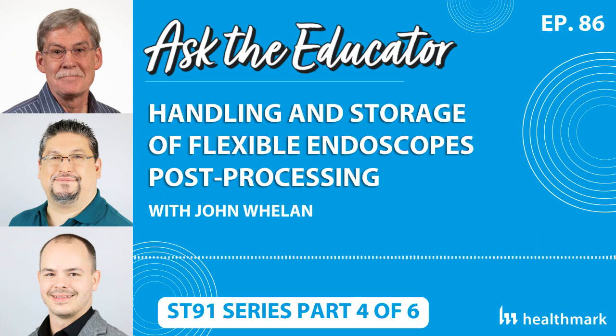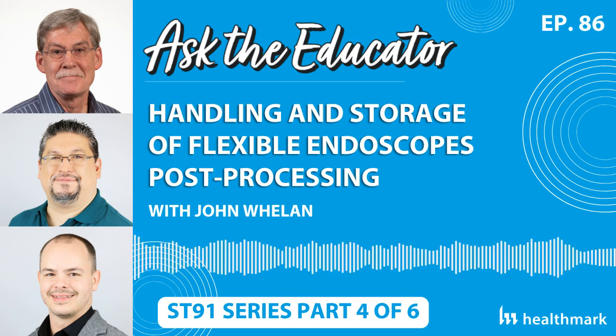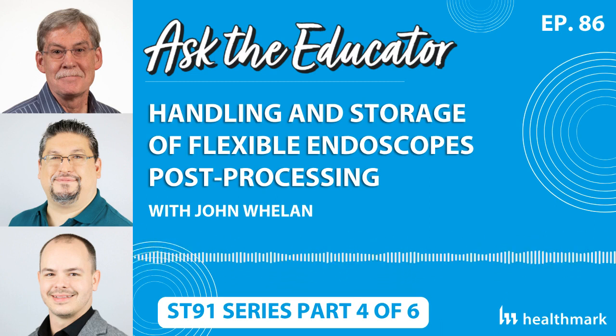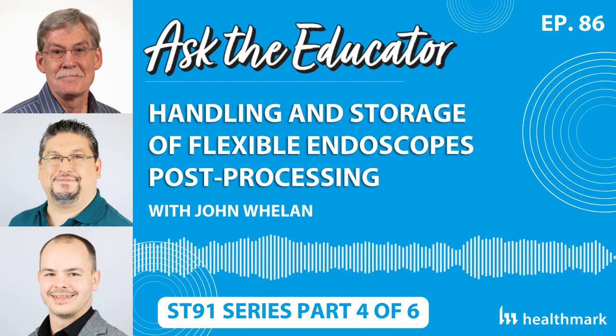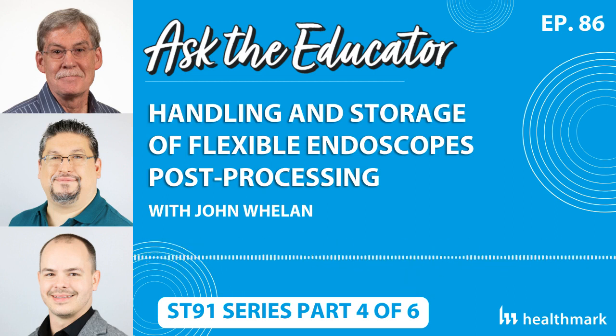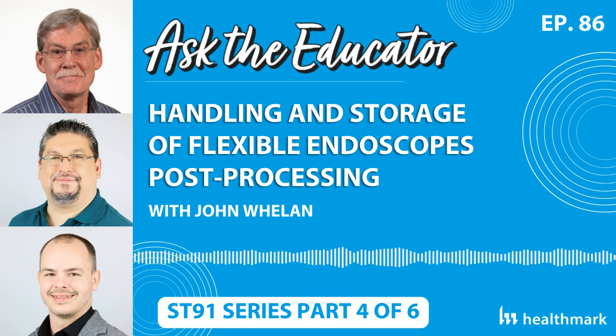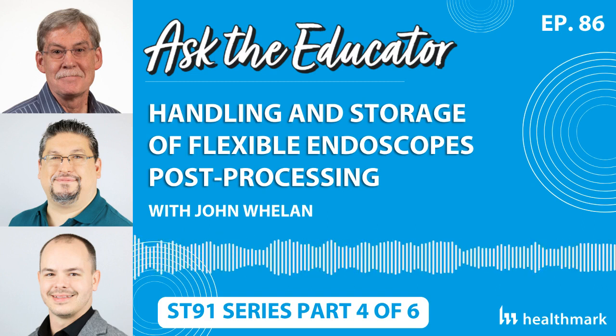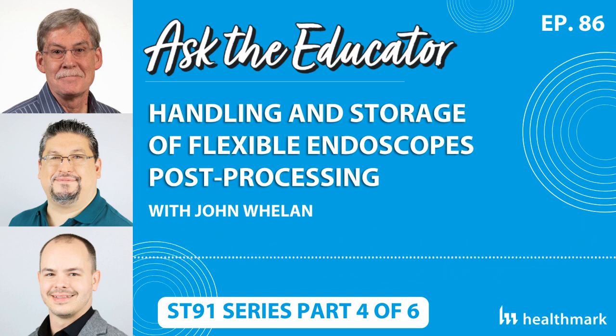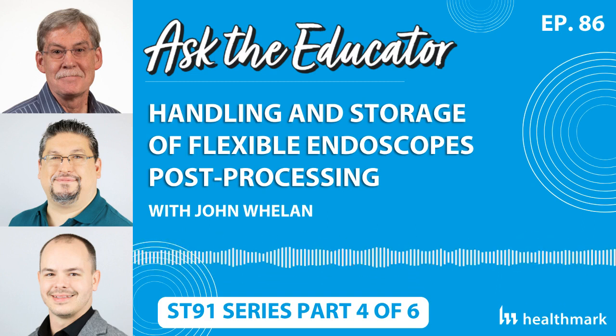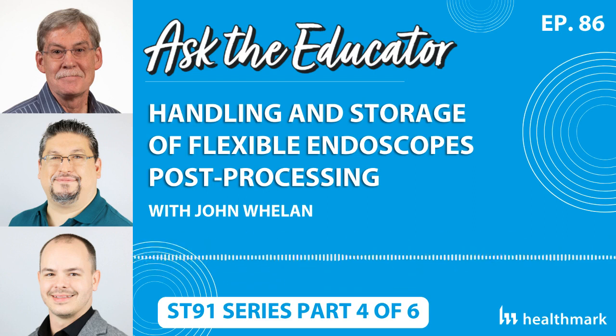So the other thing to reinforce, and this isn't anything new, this has been in other standards and guidelines before this, is no endoscope storage in a procedure room. And ideally, it would not be in the processing room unless you have a complete dirty to clean flow in a one room processing room. And then it would be at the very cleanest end of that space. But the preference is that it's in its own clean storage room.